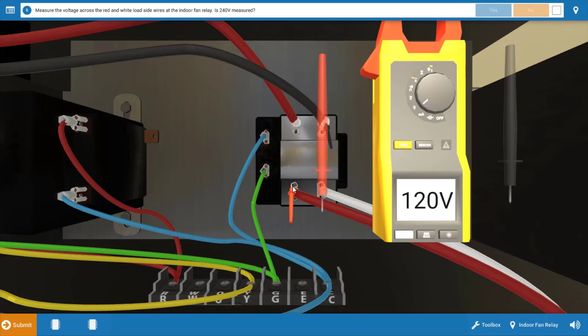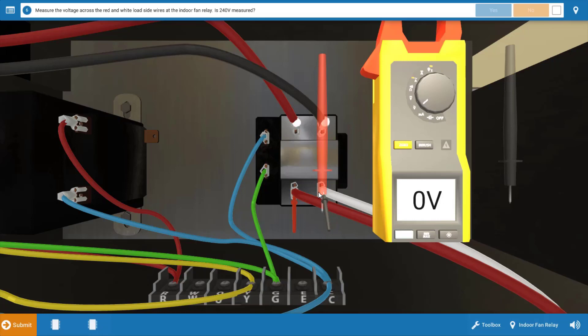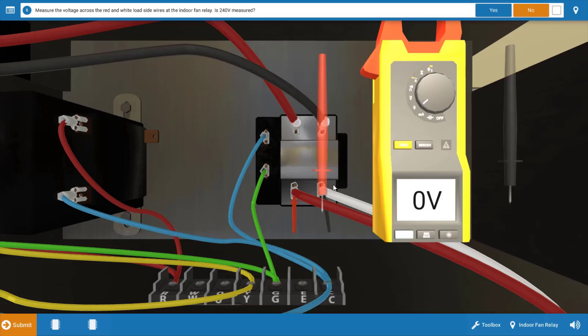Our next step is to see if we have 240 volts coming out of the relay at the load side. Now, with the 24 volts to the coil, the coil should be energized and it should be closing the contacts between the line and load side. But when we place our meter leads on the load side of that relay, we get zero volts, meaning the two sets of contacts in between the red connections and black connections here or the line and load side are open.